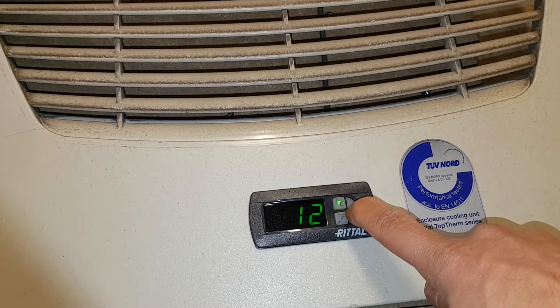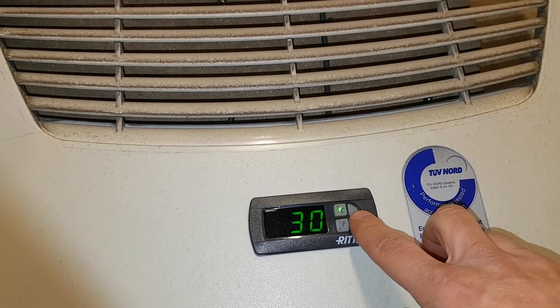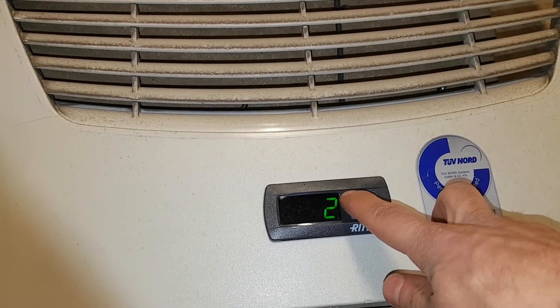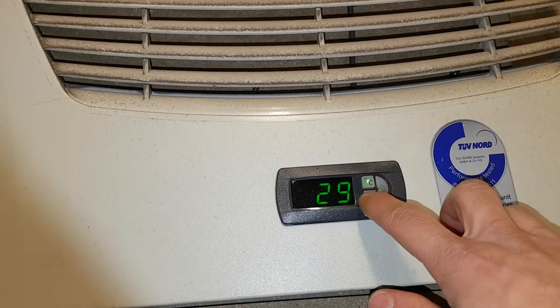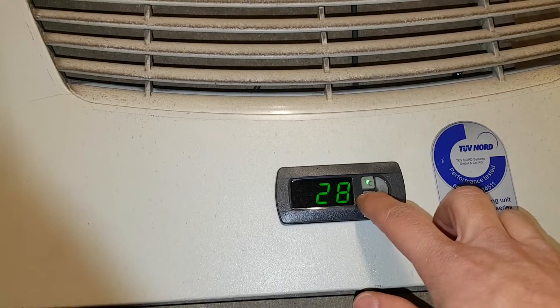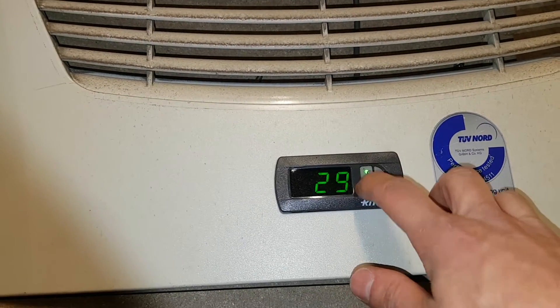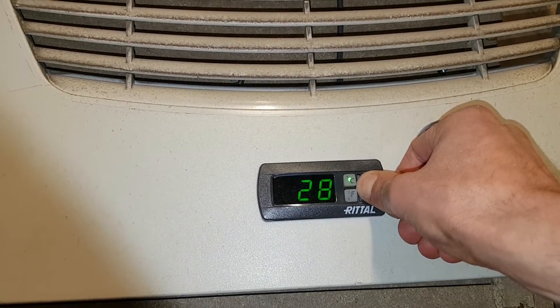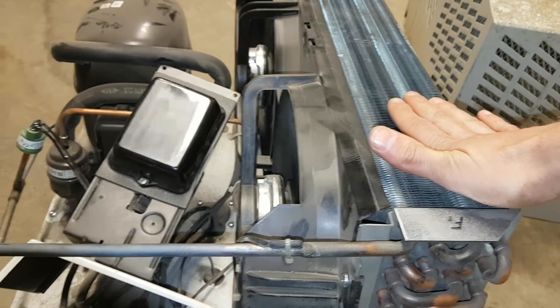I'm trying to see the set point - the set temperature is on 30 degrees. So why does it go down to 12? If you want to change the set point, you use code 22. Then you can change it - I'm just showing it for those who don't know. I had to look it up in the manual. But it doesn't follow the set point - why? We have the acknowledge. So it's not following the set point.